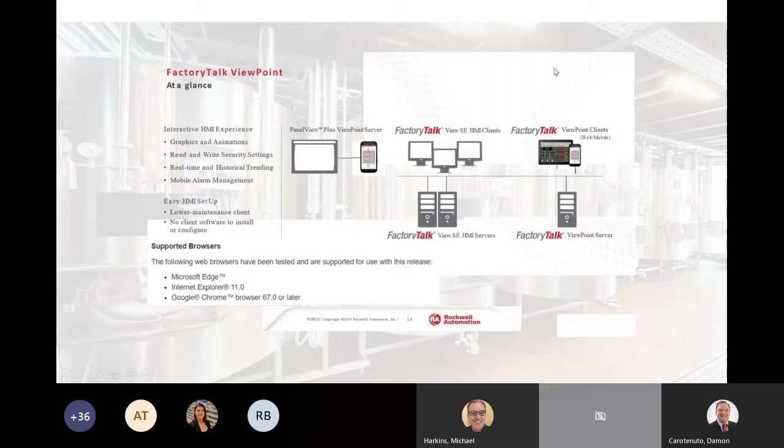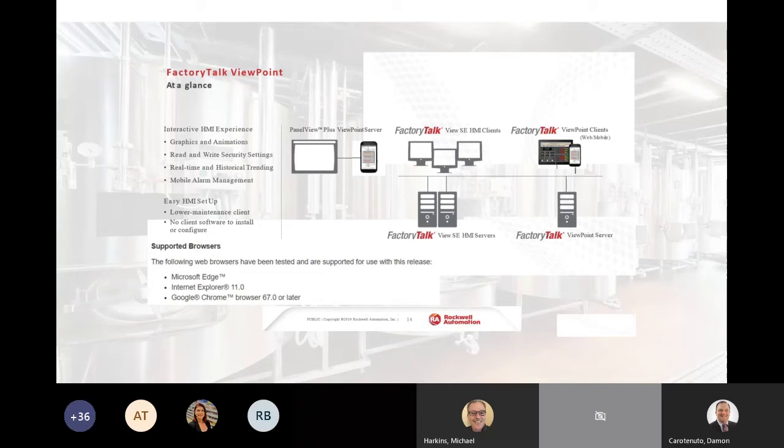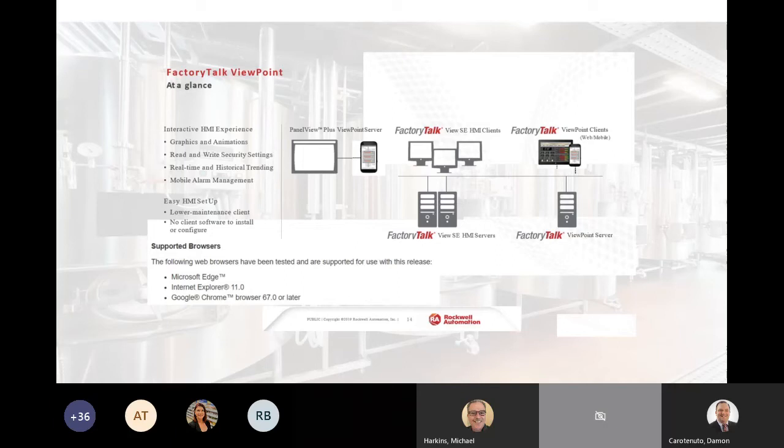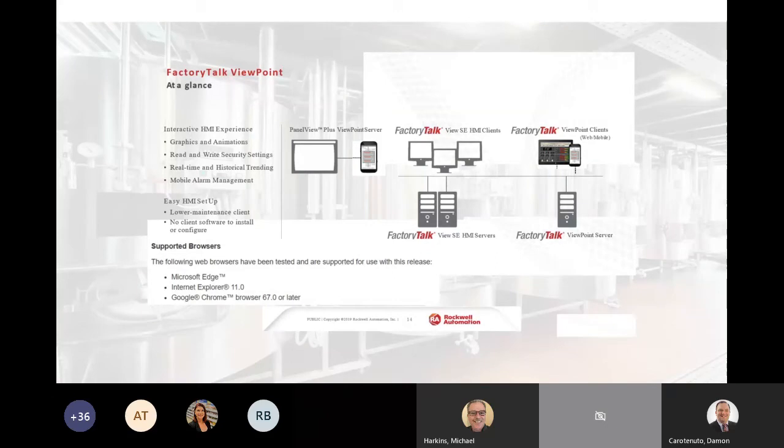So first off, here's a single line of an SE application. On the left there, you'll see a PanelView Plus and a Viewpoint server. That's all in one. That's your PanelView Plus 6 or Plus 7 with the firmware embedded in it to host a Viewpoint server. The SE application, you can see it has redundant HMI servers. It has a Viewpoint server. It has our typical SE, which if you use Factory Talk View Studio SE, you're familiar with that. They connect to the servers in a local fashion. But we also have our Viewpoint server now, which would be the server that hosts the web page application for all the mobile clients or the Viewpoint clients.